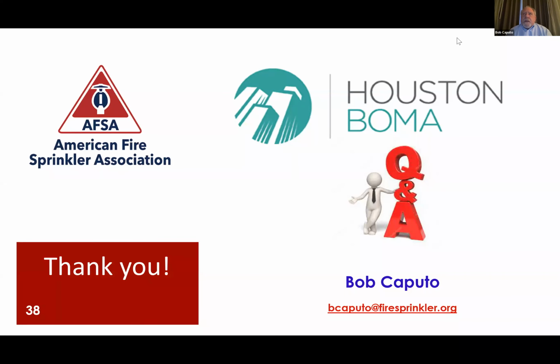If you've got flammable combustible liquids that are just being stored, there are what we call control areas. Each building's allowed to have up to 4 control areas, and the amount of each one of those is limited in each control area. I talked about commodities earlier and how we protect those. Well, with flammable and combustible liquids, based on the flash point, they're listed or classified as flammable liquids 1A, 1B, 2A. If they're combustible, then those are also classified as 3A and B and so on.